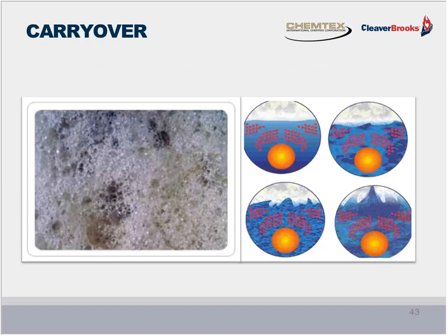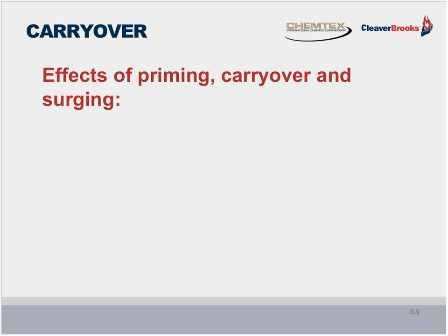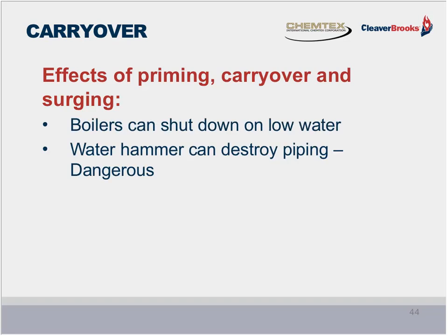And Steve alluded to carryover, and this is an important thing that in my years of experience, I've talked to so many different customers about this that it's definitely worth spending some more time talking about. And obviously, the effects of priming and surge and sink and swell that Steve talked about: our boilers can be shut down on low water cutoff. You can have water hammer, which can destroy piping and be dangerous to personnel.